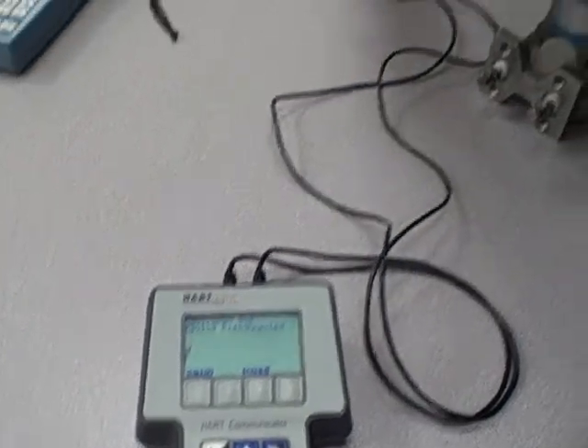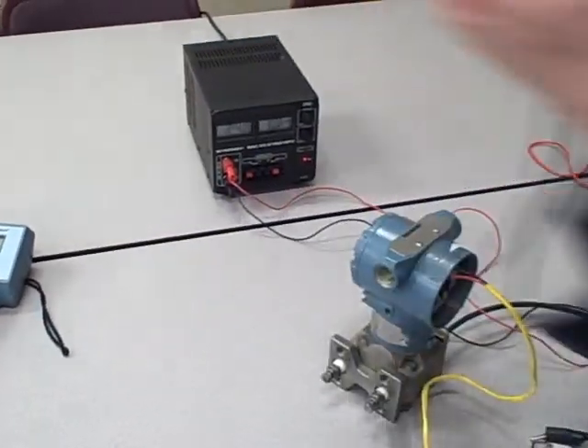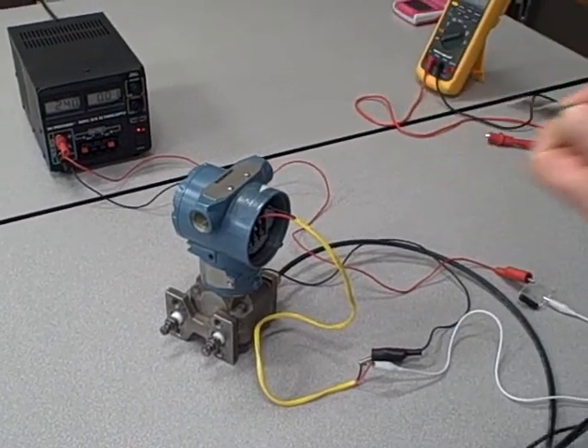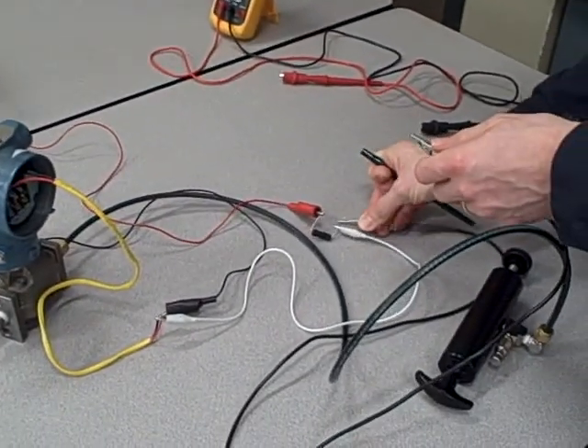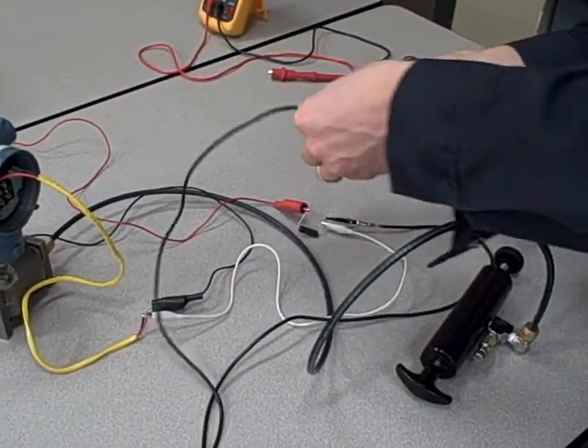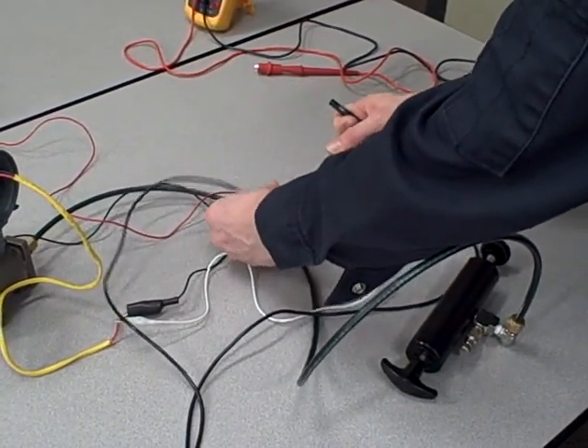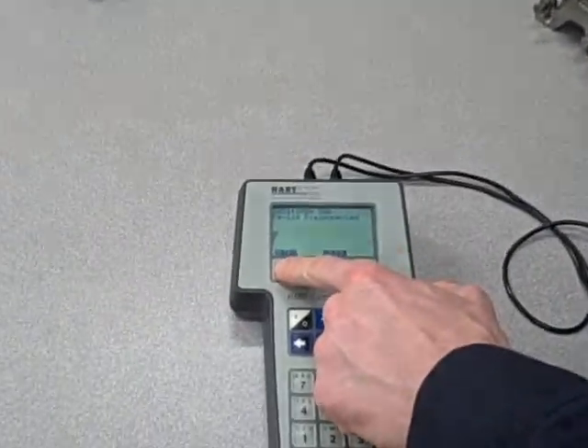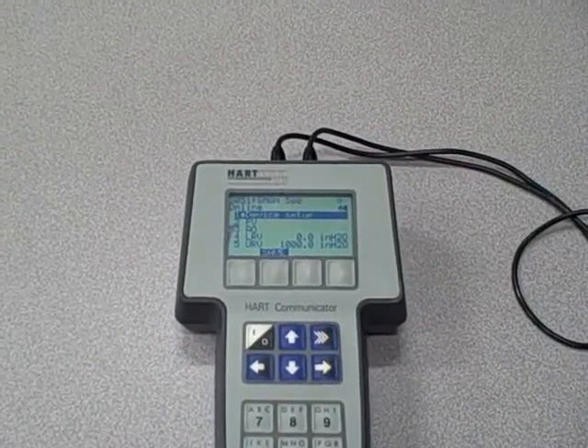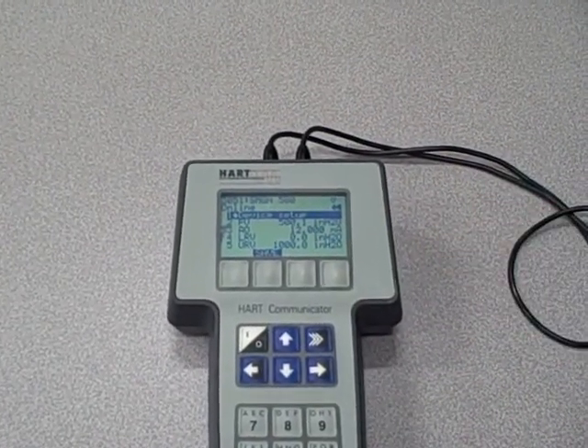Now here's another place you can connect the communicator. You can go directly in parallel with the loop resistance. It may not make sense at first why this works. I'll first demonstrate that it does work. I'll push the retry button, and here we are again. It's now reading the same variables.